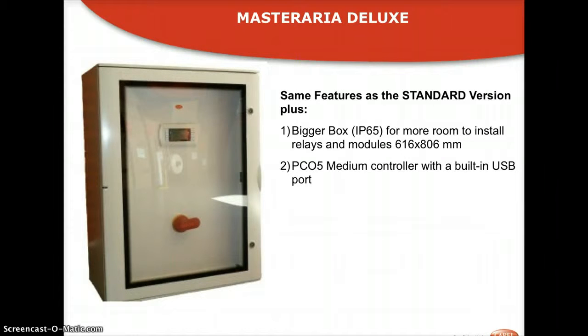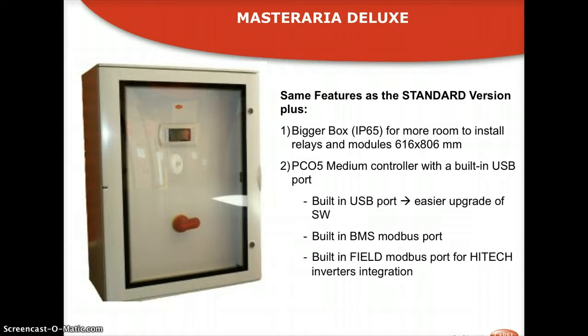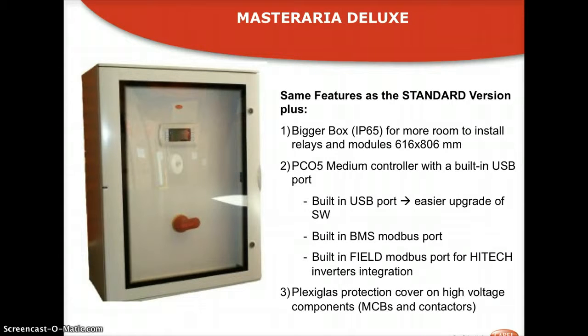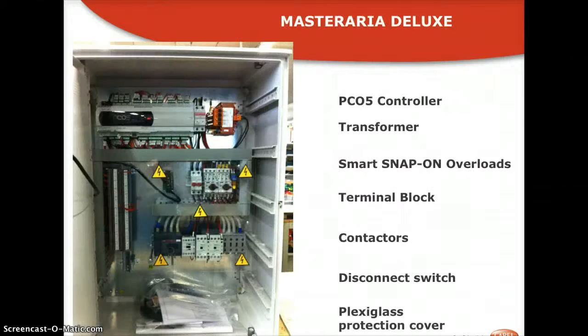As I said, it contains a PCO5 Medium which has got the same identical inputs and outputs of the PCO3. However, it has got a built-in BMS RS485 port for Modbus communication and a field port embedded for the inverter integration. It also has a plexiglass protection cover to protect the high voltage components like MCB and contactors, which you can see here on the top, onto the back plate.